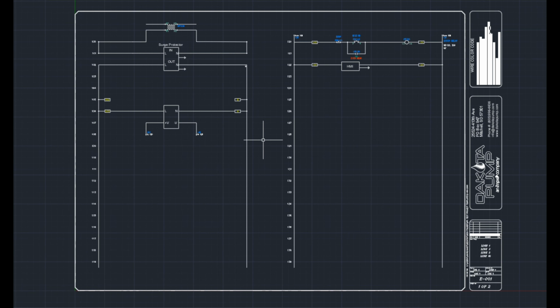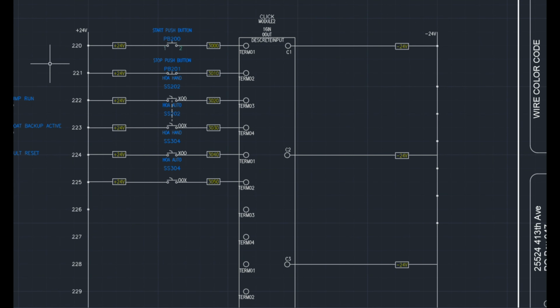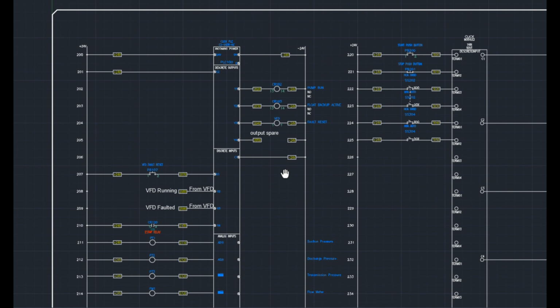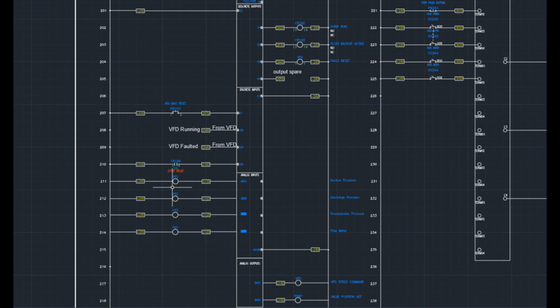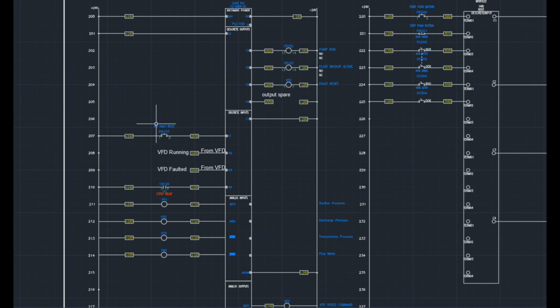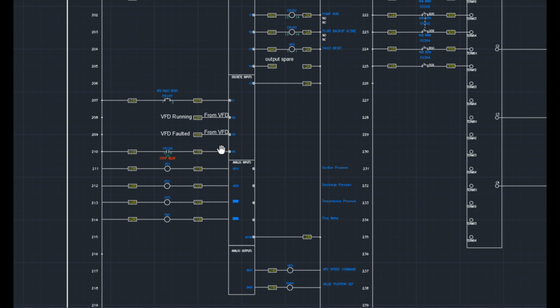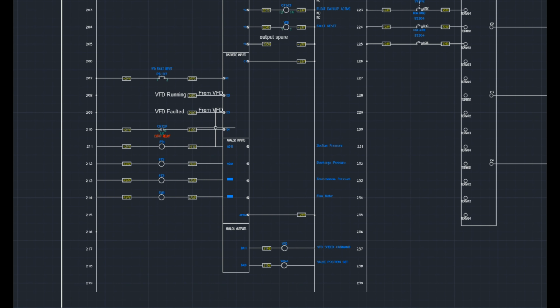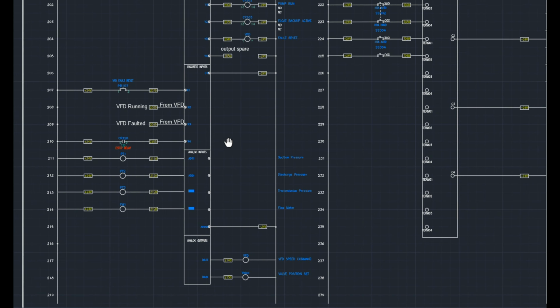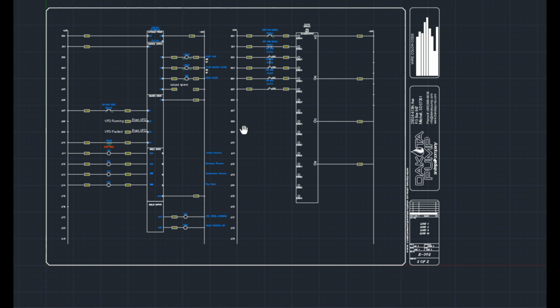Here is my as-built. So everything in these next few pages will be as everything is in the panel right now. So like I said, everything in here is the same. So we'll just move on to the second page. This here is the new PLC. As you can see, we have more analog inputs, but other than that, everything else is basically the same. I had to move my pressure transmitters to this analog input section of the PLC because I had no more analog input modules to use.